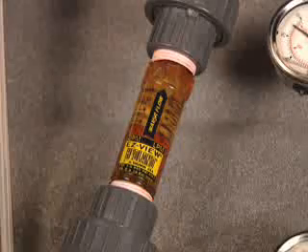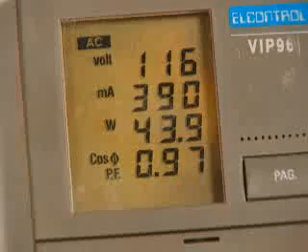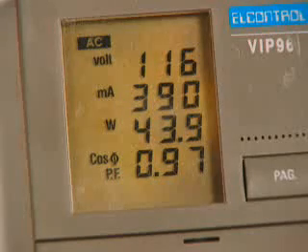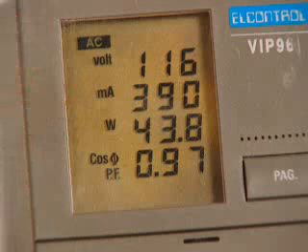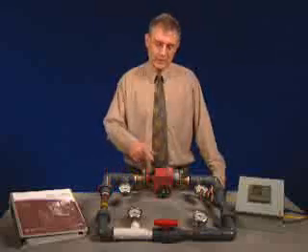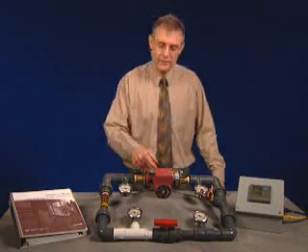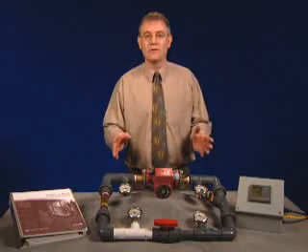We haven't throttled the valve, so we have not caused any pressure drop in the system. We're now running at 44 watts, so we've gone from 73 watts to 44 watts, a savings of 29 watts versus the 5 watts we saved using the throttling valve. By slowing the system down, we can usually achieve savings 5 to 6 times higher than using the throttling valve. And that means savings to your organization.